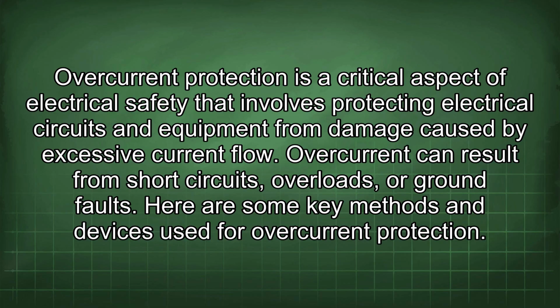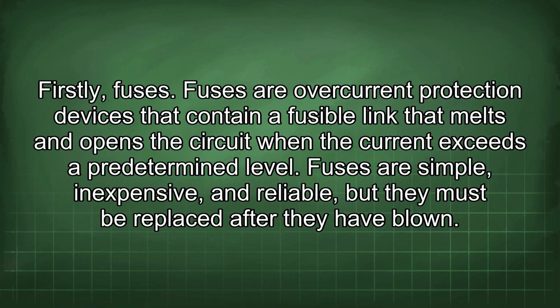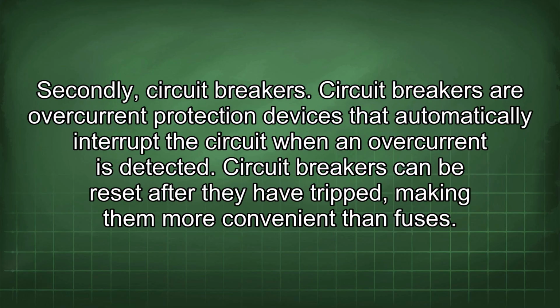Overcurrent protection is a critical aspect of electrical safety that involves protecting electrical circuits and equipment from damage caused by excessive current flow. Overcurrent can result from short circuits, overloads, or ground faults. Here are some key methods and devices used for overcurrent protection. Firstly, fuses. Fuses are overcurrent protection devices that contain a fusible link that melts and opens the circuit when the current exceeds a predetermined level. Fuses are simple, inexpensive, and reliable, but they must be replaced after they have blown. Secondly, circuit breakers. Circuit breakers are overcurrent protection devices that automatically interrupt the circuit when an overcurrent is detected. Circuit breakers can be reset after they have tripped, making them more convenient than fuses.